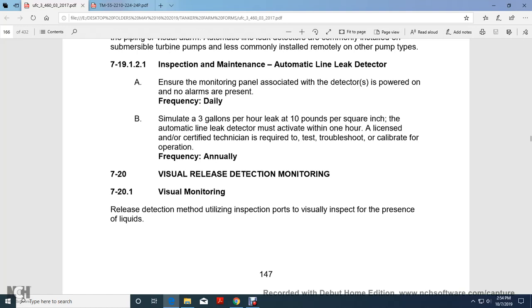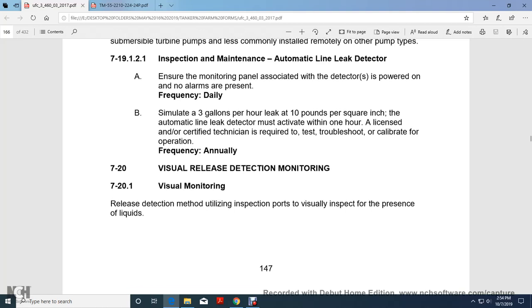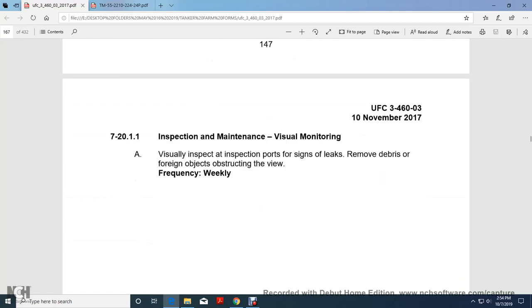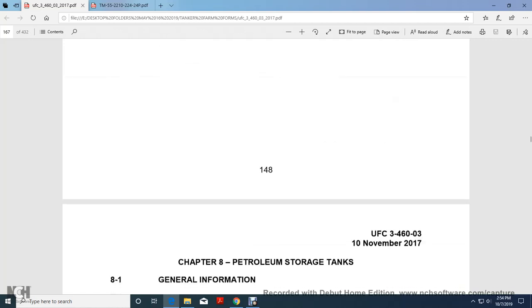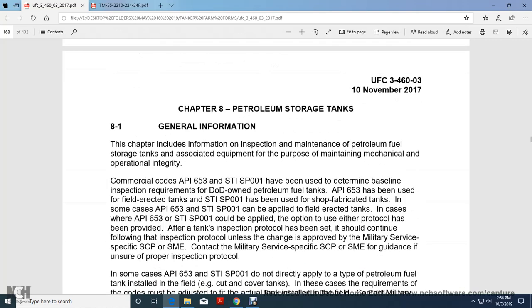7-20 visual release detection monitoring. Visual monitoring is a release detection method utilizing inspection ports to visually inspect for the presence of liquid. 7-20.1.1 inspection maintenance visual monitoring: visually inspect inspection ports for signs of leaks, and remove debris and foreign objects obstructing the view, frequency weekly. Chapter 8 Petroleum Storage Tanks.